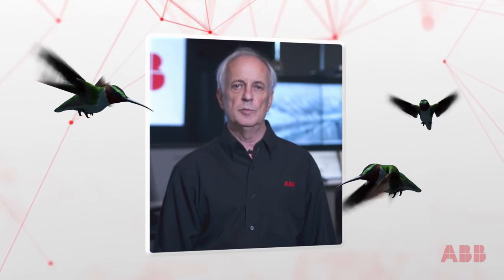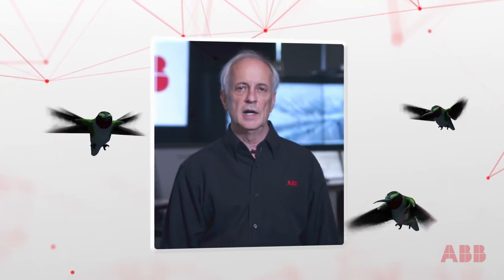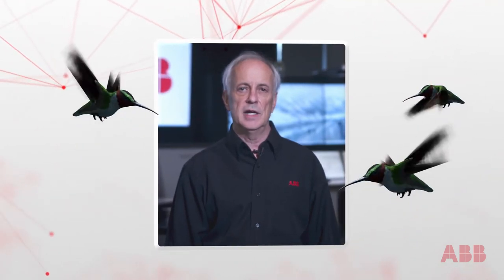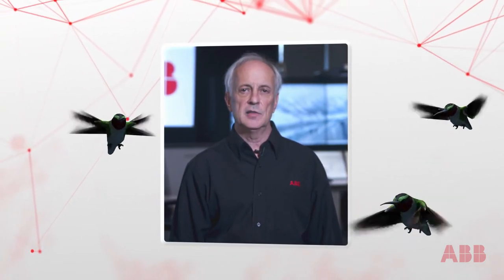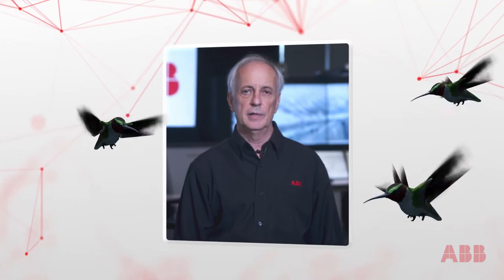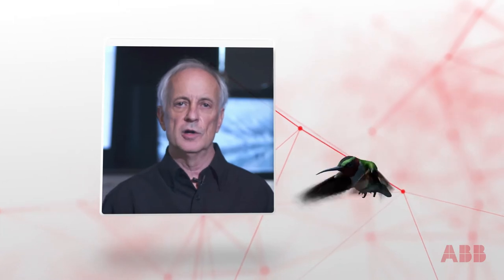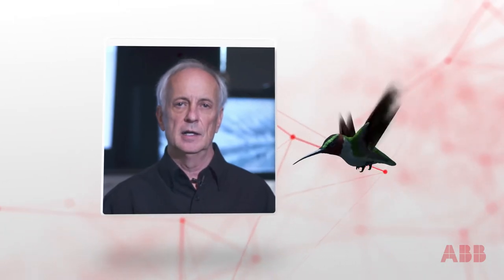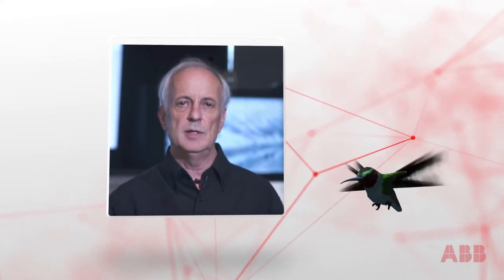Additionally, this procedure can be performed by a field technician with minimal training, utilizing only a laptop connected to one of ABB's standard Smart Junction Boxes, or SJBs. You literally connect to the SJB directly from your laptop and execute the ABB Adaptive Smart Commissioning procedure. Loop commissioning results are automatically documented and can be transferred to third-party completion systems. Finally, ABB's late binding technology allows for automatic and rapid coupling between the applications and the associated I/O hardware.